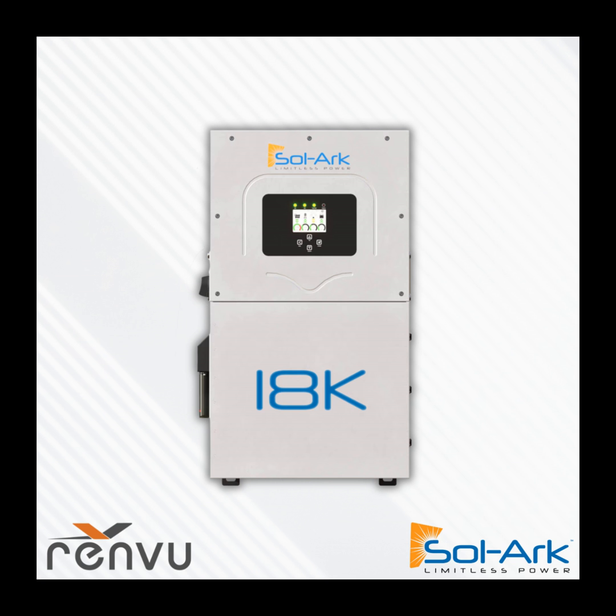So adding some amount of backup power to these commercial projects does sell the project. But then it's like, well, how do I eliminate the risk of whole building backup? And it's, well, don't do it. With commercial, you don't have to. Just do essential backup. And what that means is you're going to have less amperage flowing through the inverter. So if there is some kind of externality, like an overloaded inverter during a grid failure, you're far less likely to damage the inverter by not overloading the inverter.